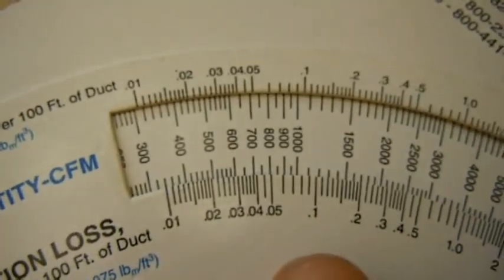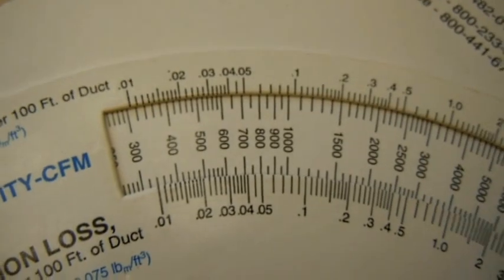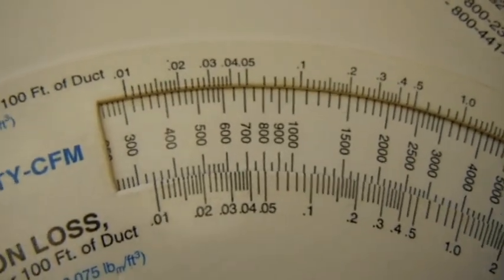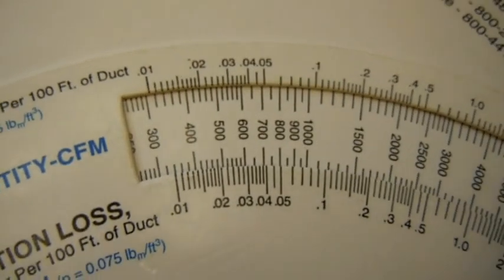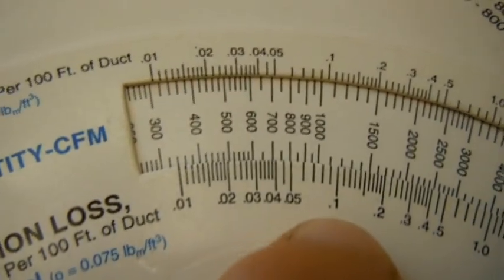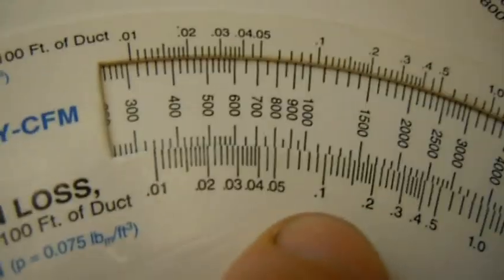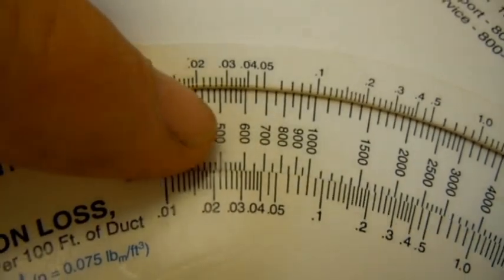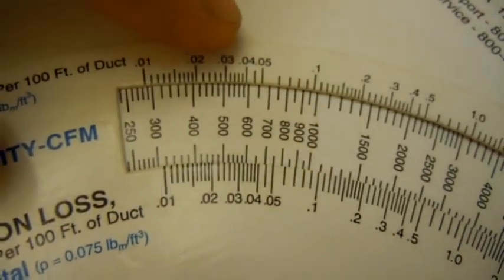When calculating the supply duct, still always go with manufacturer specifications. Rule of thumb is you can go with a .1 for the friction loss and still 400 CFMs per ton.